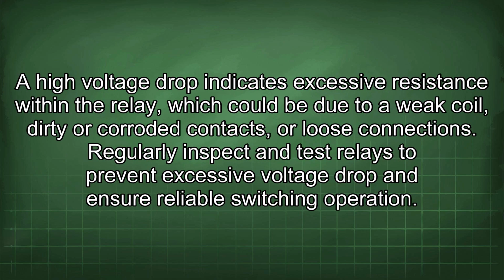A high voltage drop indicates excessive resistance within the relay, which could be due to a weak coil, dirty or corroded contacts, or loose connections. Regularly inspect and test relays to prevent excessive voltage drop and ensure reliable switching operation.